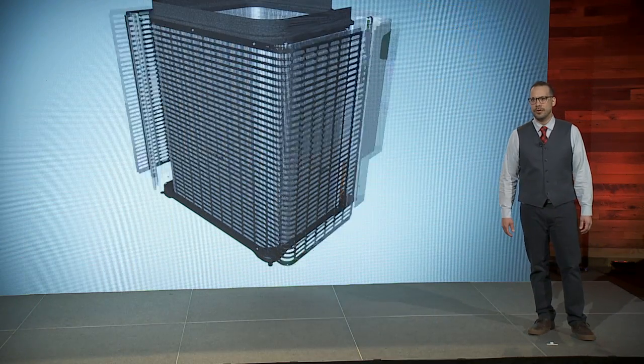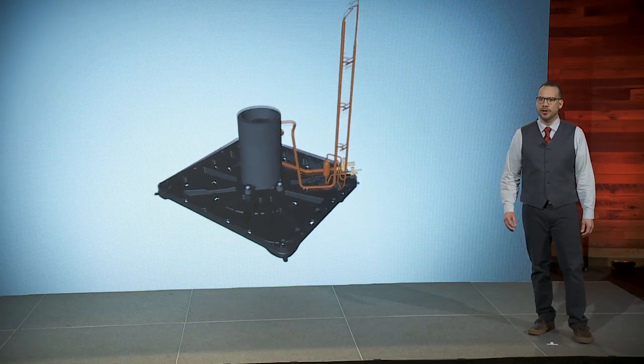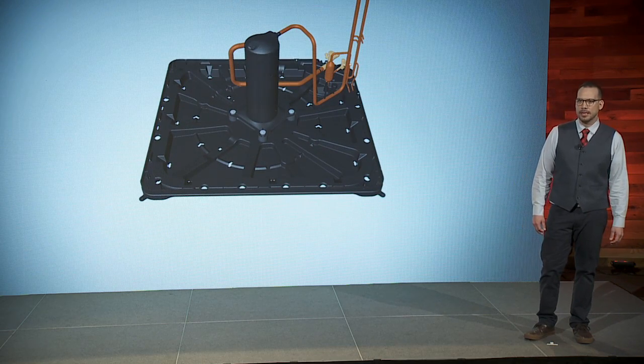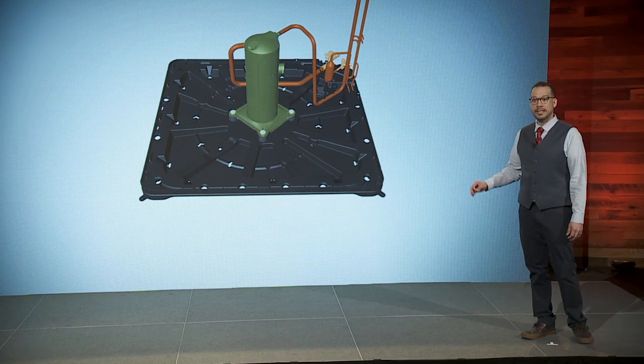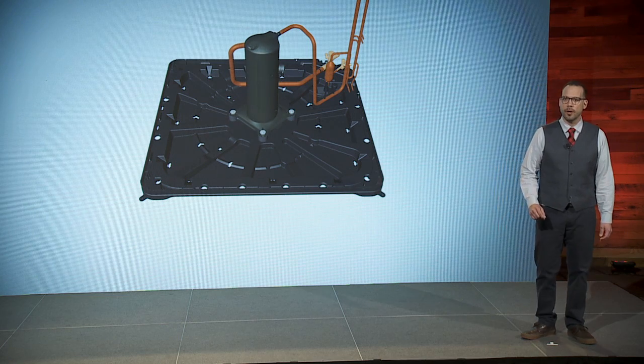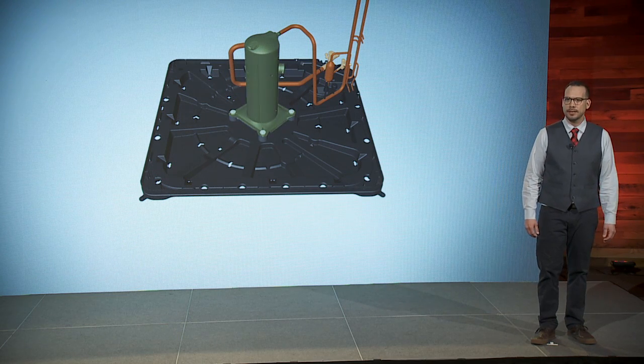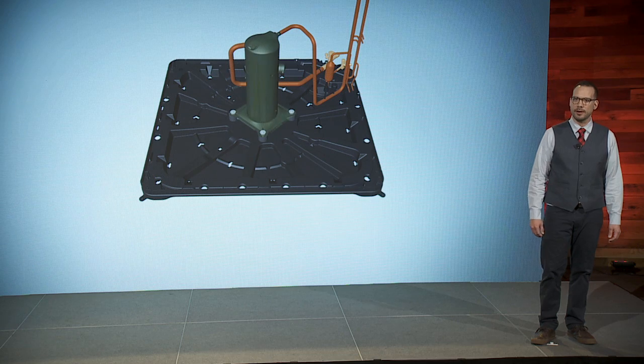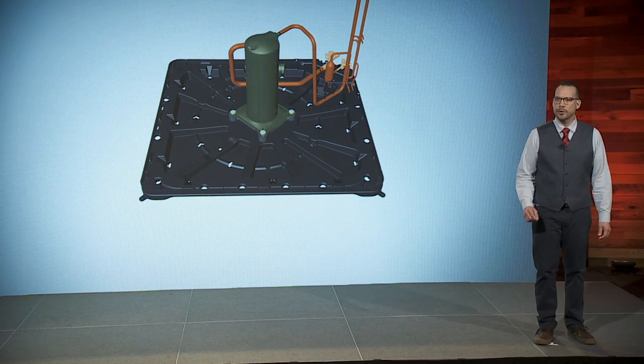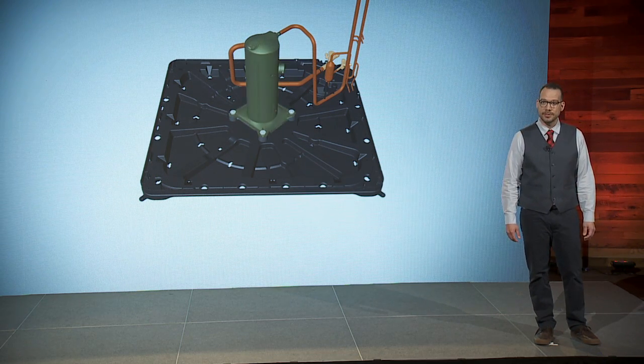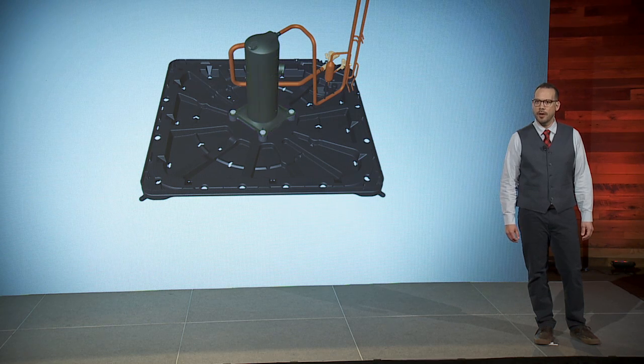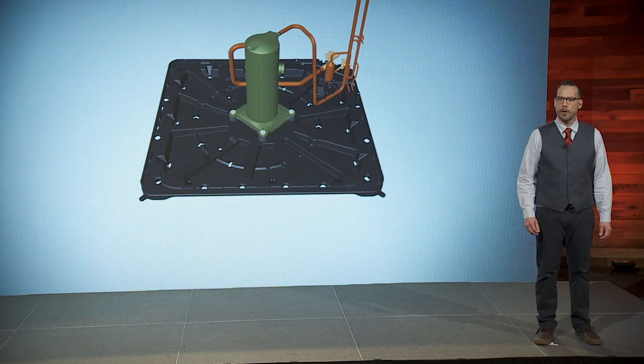As with the outdoor and indoor fan motors, the compressor is also driven by the demands of the home. Depending on the conditions, both inside and outside the home, the system can run at a fraction of its full capacity to maintain comfort while still saving on electricity. This means fewer high-intensity starts and stops, more consistent temperatures in the home, and better control of the home's humidity levels. The variable capacity operation uses up to 80% less electricity than your conventional PSC blowers typically found in base model air handling units.